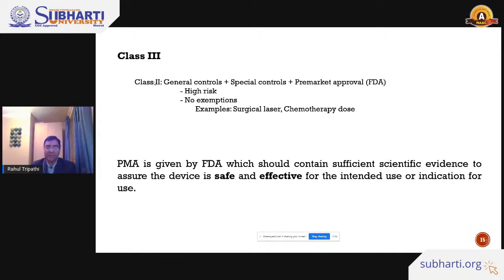Pre-market approval is given by the FDA, and it should contain sufficient scientific evidence to assure the device is safe and effective for the intended purposes, or for the indication for the users, basically. And this is where pre-market approval, PMA, comes into the picture with class 3. So just remember, for class 1, general control is needed and you can get exemption; the manufacturer can get exemption from the 510(k) form. Whereas for class 2, sometimes 510(k) forms come into the picture, with moderate risk associated, whereas class 3 has general control, special control, and pre-market approval. PMA is needed for commercializing any medical device product in the US market, according to the FDA.